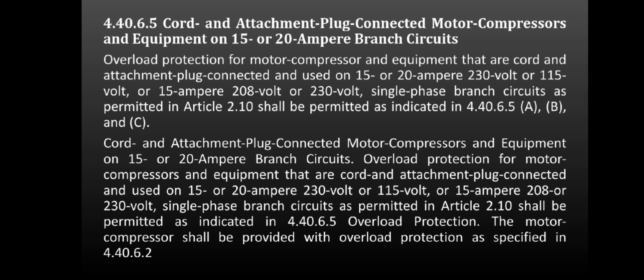So these slides describe the added rules for motor compressors that are plugged into outlets instead of being hardwired. They still need overload protection similar to hardwired units. The plug and receptacle used must not exceed a certain amperage rating for safety: 20 amperes at 125 volts and 15 amperes at 250 volts. The protective device must have enough time delay to let the motor start without instantly tripping. Basically, this slide highlights that plug-in motor equipment must follow strict rules to prevent electrical accidents.